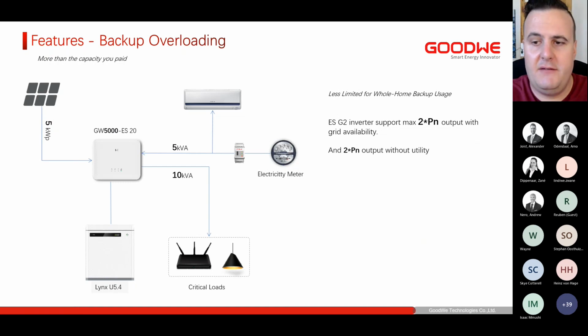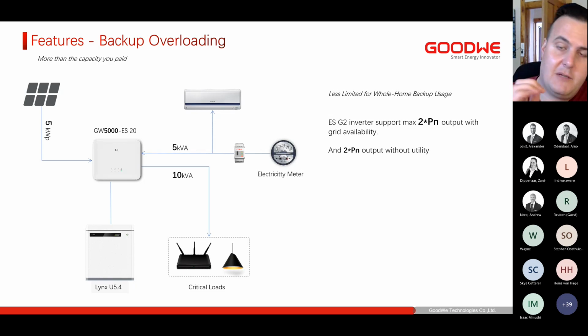And as I explained, that overload is a constant overload when you have utility available. So it can take 10 kilowatts from the grid, or 5 kilowatts from the grid and 5 kilowatts from the PV. But it can also simultaneously take 5 kilowatts from the PV and 5 kilowatts from the battery to give us that 10 kilowatt overload.